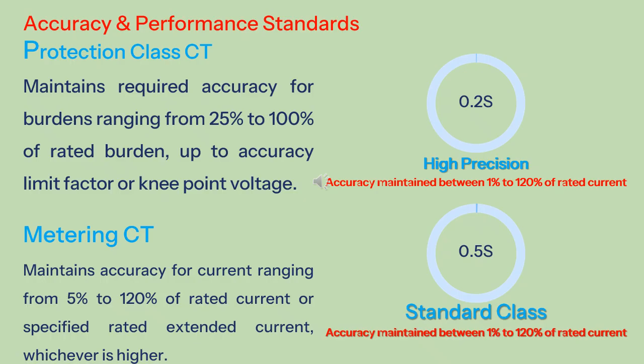Accuracy and performance standards. Protection class CT: maintain required accuracy for burdens ranging from 25% to 100% of rated burden up to accuracy limit factor or knee point voltage. Metering CT maintains accuracy for current ranging from 5% to 120% of rated current or specified rated extended current, whichever is higher.